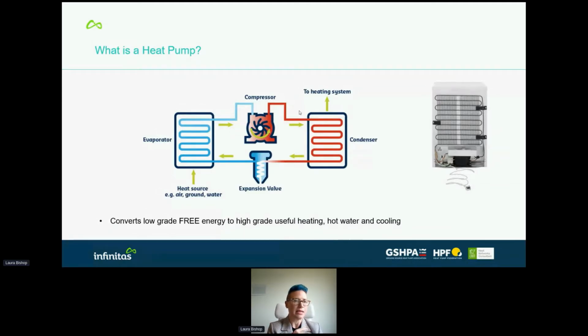Basically the system works by heating and cooling refrigerant, in gas or liquid form, to transfer energy from a cold source to a hot source. And when I say cold, we can take air or water at minus 10, minus 20, and still produce hot water, because of the amount of energy still available even at minus 10, minus 20, minus 30. It converts that low grade free energy from water, air or ground into high grade useful heating, hot water and cooling. On the right hand side there, that's the back of a fridge.